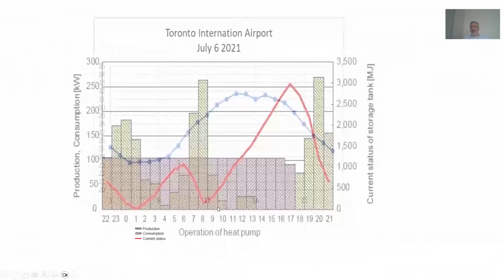Again, moving back to our cycle. These yellowish ones are the demand, and the pink one is the production line. So what is happening there? You run a machine continuously, let's say 17 hours a day. This machine running has no direct correlation with your demand load, because you are using this CO2 heat pump to charge the tank which is supplying hot water to the facility. So these peaks, yes, but when we are designing our system, we have to make sure that these peaks are met and your storage is good enough to meet those peaks. That's the intent of this one.